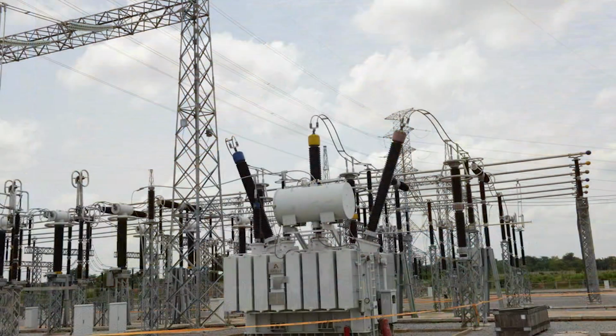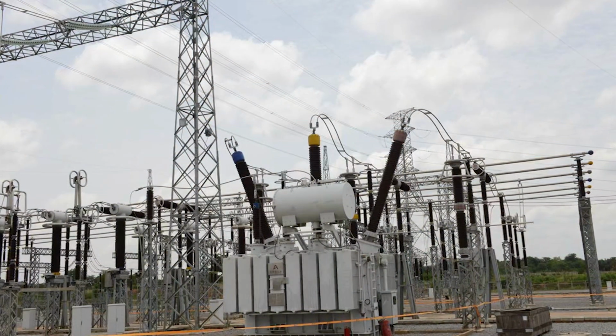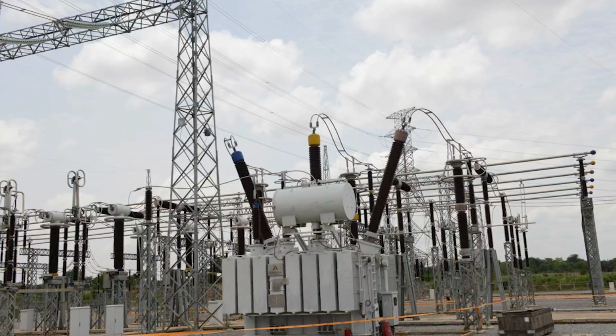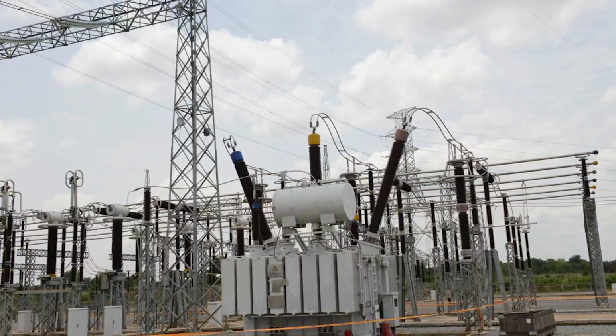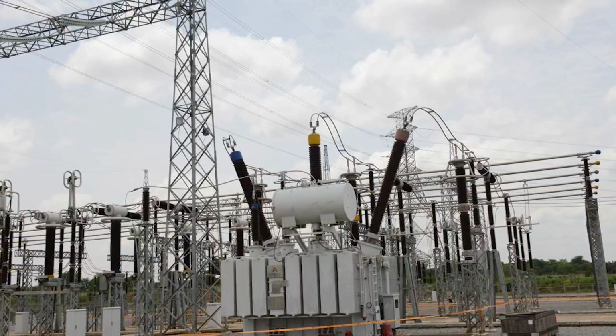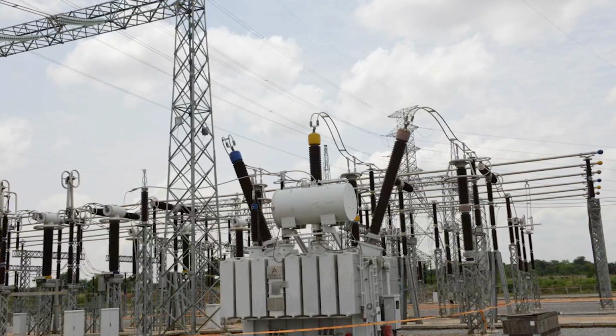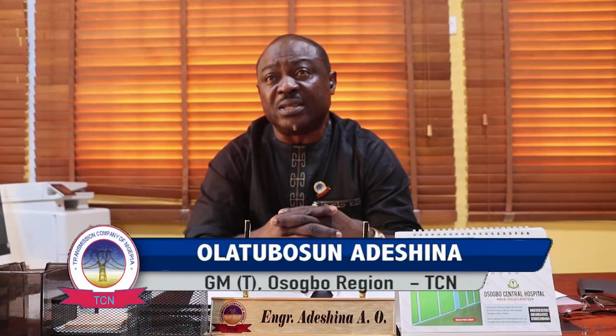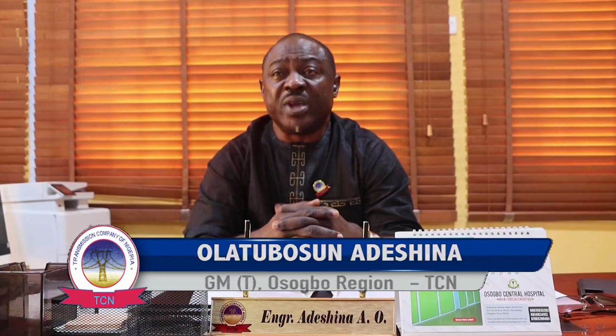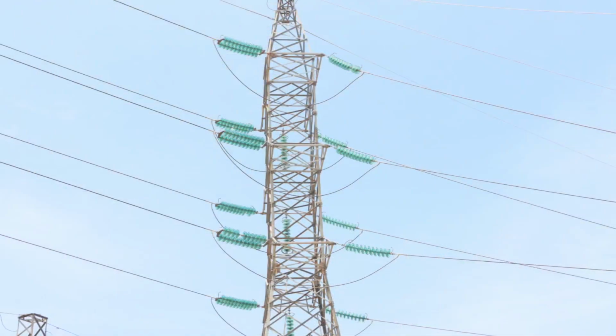At Jericho, at Ibadan there, we are undergoing installation of a 100 MVA transformer, which will increase the capacity of that station from the present 40 MVA to 140 MVA towards Ekiti and Ondo states. At the moment, we are feeding those two states on the Osogbo Akure 132 kV line, and by extension from Akure we have another line going to Ado-Ekiti. This presently caters for the load of Ondo and Ekiti states.